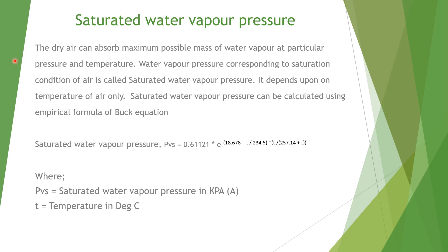Saturated water vapor pressure can be calculated using the empirical Buck equation. PVS equals 0.61121 times e to the power of (18.678 minus T divided by 234.5) times (T divided by 257.14 plus T), where PVS is the saturated water vapor pressure in kiloPascal absolute and T is temperature in degrees Celsius.